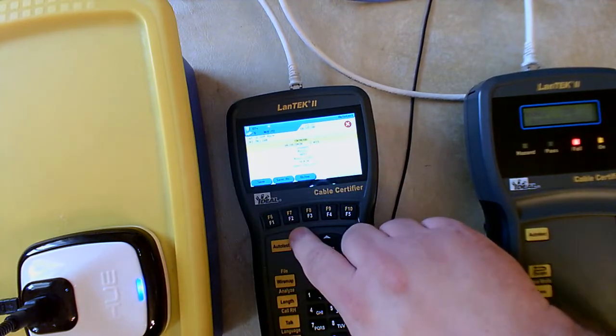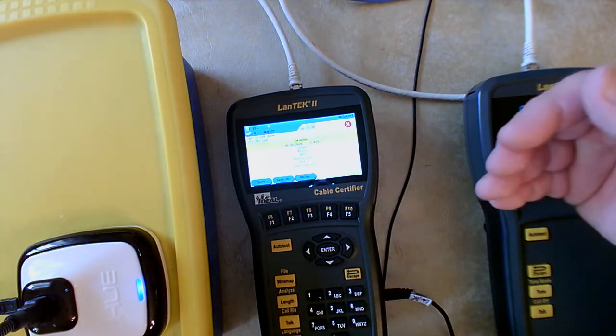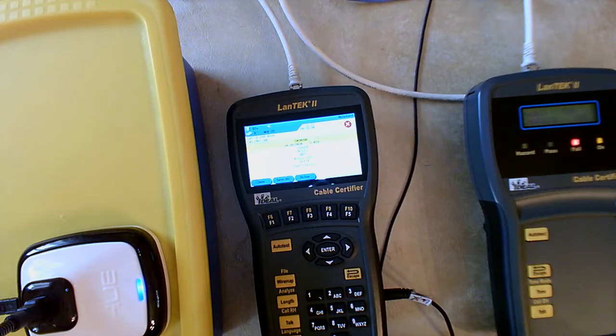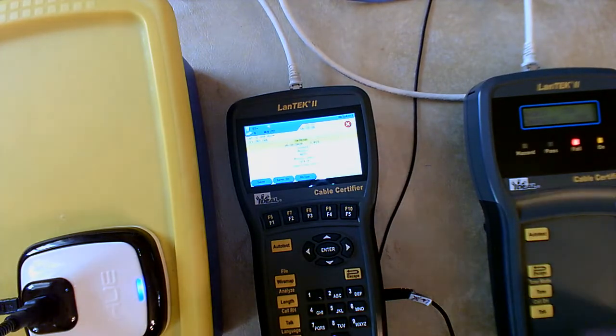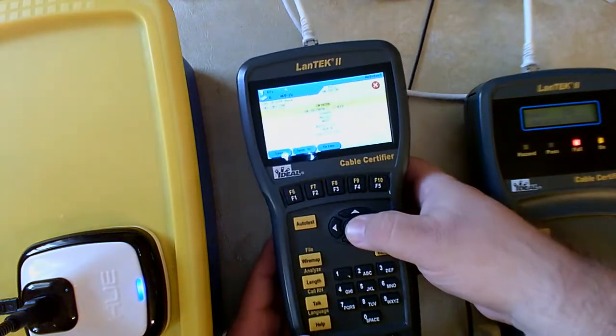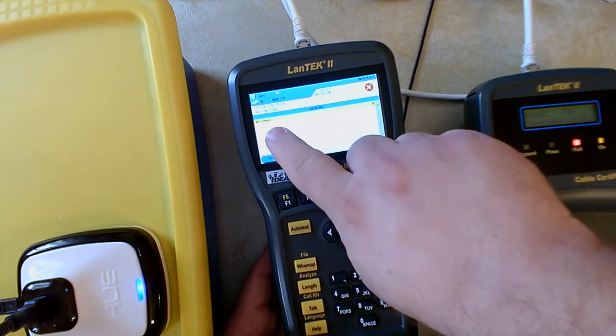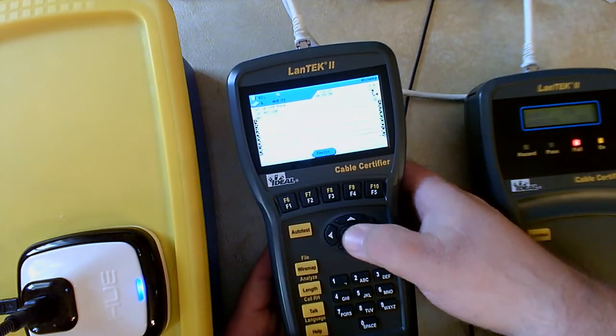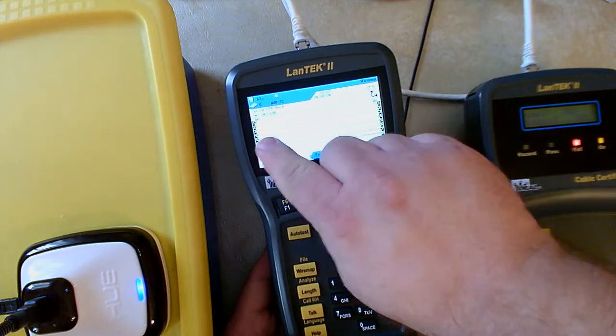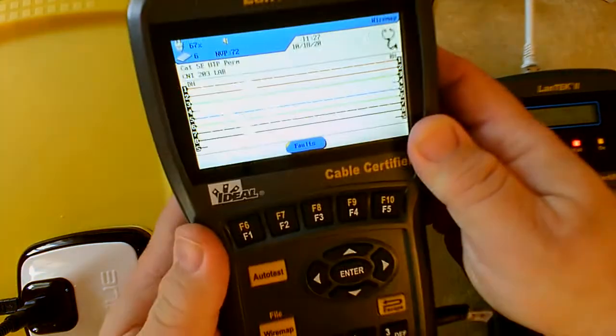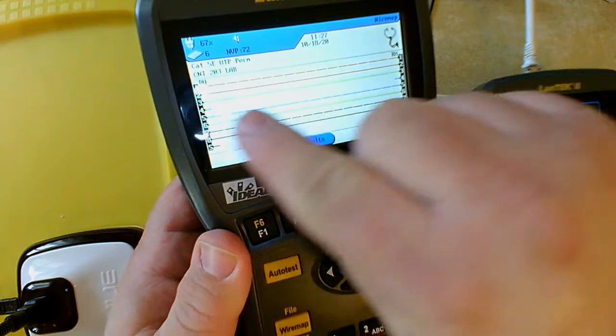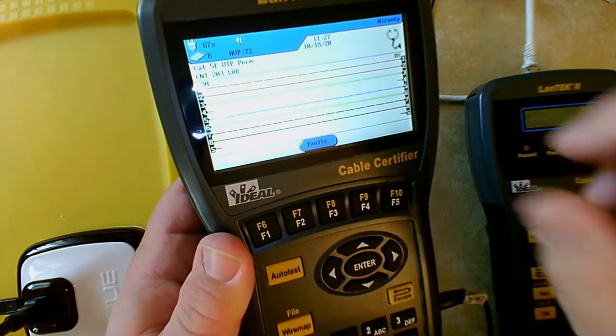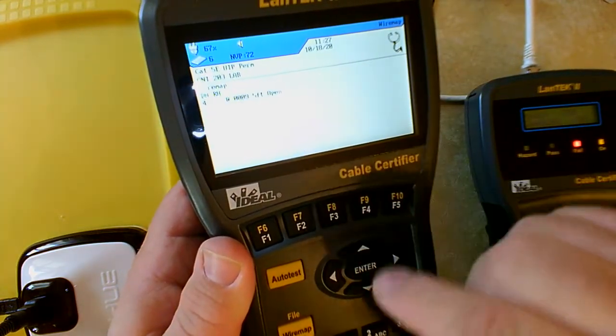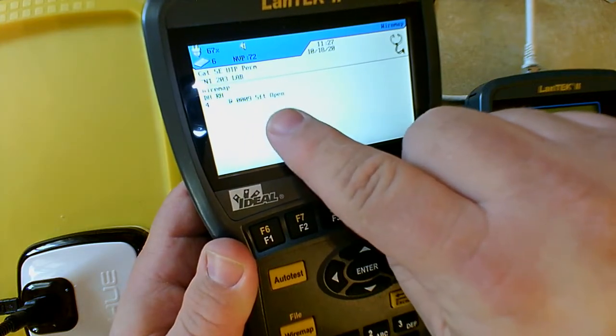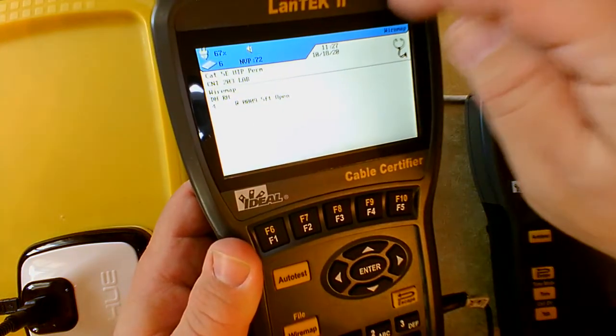I would save the results, take note of this run, and come back later to troubleshoot it. If I look at the results here, hitting enter, you'll notice it failed the wire map. Hitting enter again shows that wire 4 is missing. So there's a problem, and I can check the fault location, which says at about 9 feet it's open.